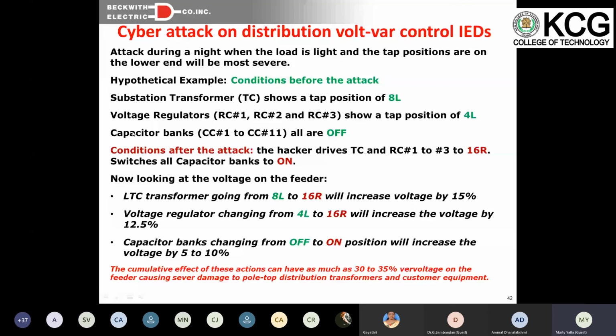If you have voltage regulators in series, those can also be raised. And if you have capacitor banks, generally at nighttime, because the load is light, the capacitor banks are off, and you can bring them on, and the voltage goes up. So if a hacker hacks into a distribution system, raises the taps and switches on the cap banks, you can have 30 to 35% overvoltage. Imagine having 300 volts on a 230 volt circuit. All your TVs, air conditioning systems, refrigerators, and all the electronic equipment get fried at such a voltage. It's very dangerous.